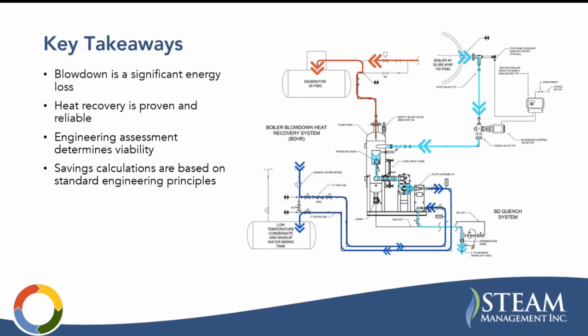I would say I would evaluate that. Again, if it is a small flow, like 10,000 pounds per hour with a good condensate return, it may not have a decent enough payback. But otherwise, with large flow, decent pressure, and kind of standard water treatment, it starts becoming a real opportunity. So hopefully that answers your question. The long answer short: you can pair the blowdown heat recovery with improved blowdown controls as well. So yeah, that's my recommendation there.